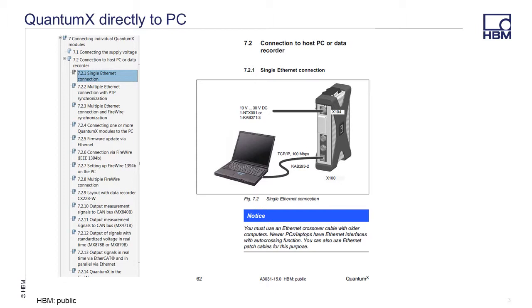If you happen to have a very old PC, a crossover cable will be required if the Ethernet interface does not have autocrossing function. The QuantumX module will also need a power supply connection.